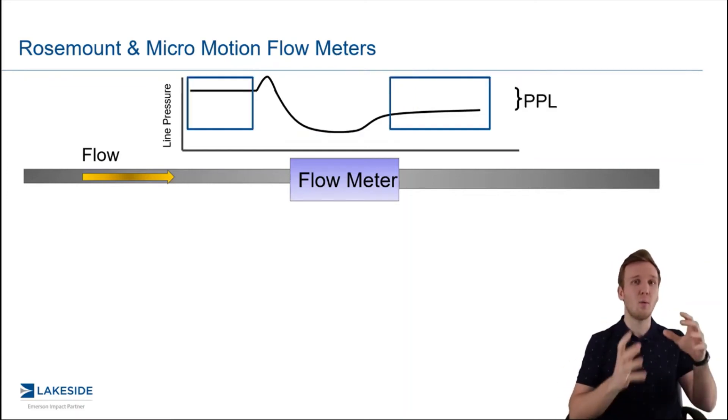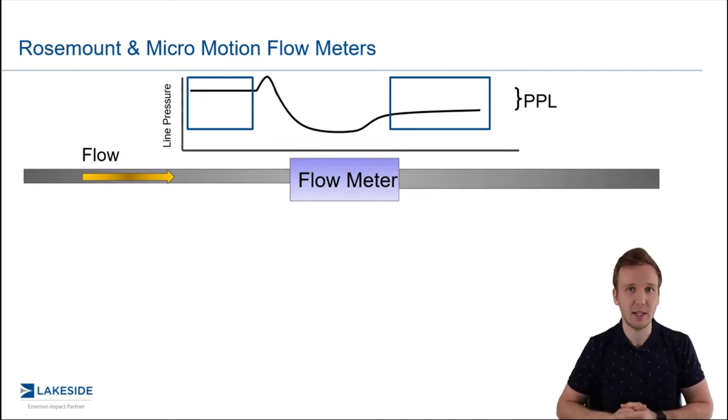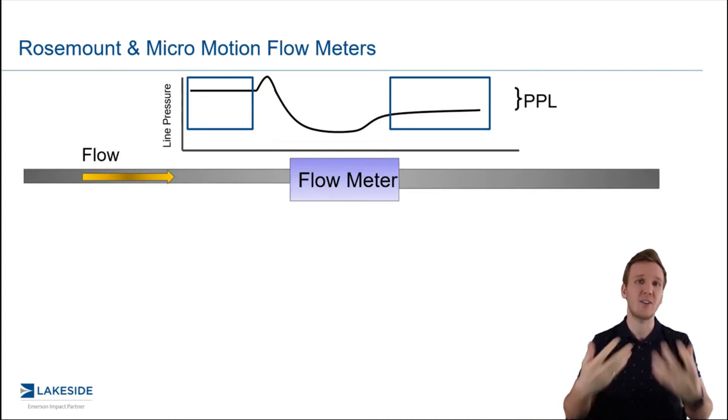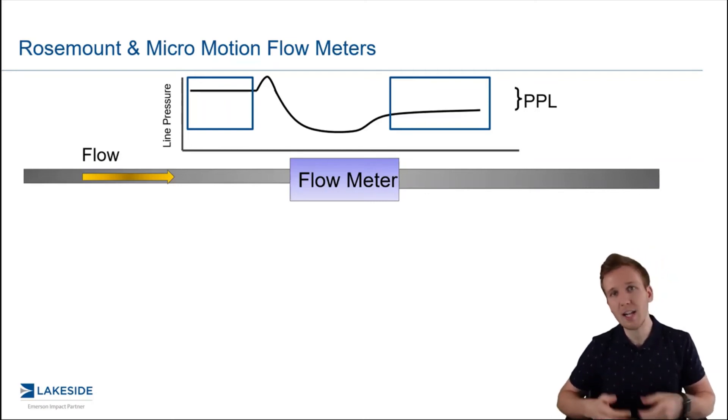Permanent pressure loss is going to be way before and way after that flow meter. And what that is going to be is the permanent effect that this flow meter has had on your system. So you got to imagine the product traveling through, it has some sort of friction or obstruction, and that's going to have a lasting effect.